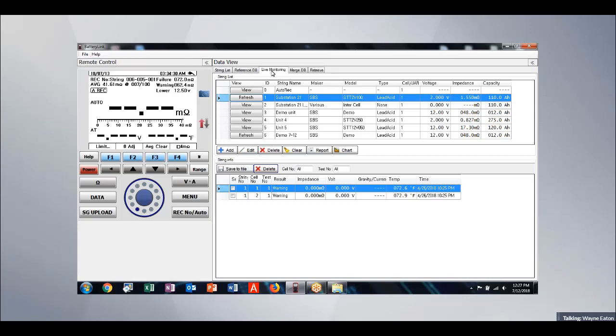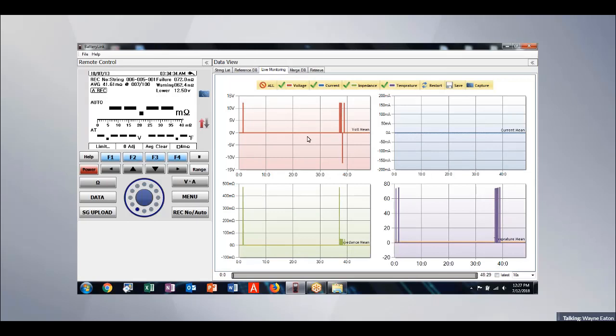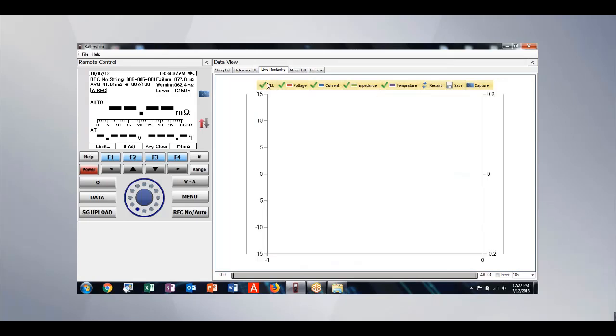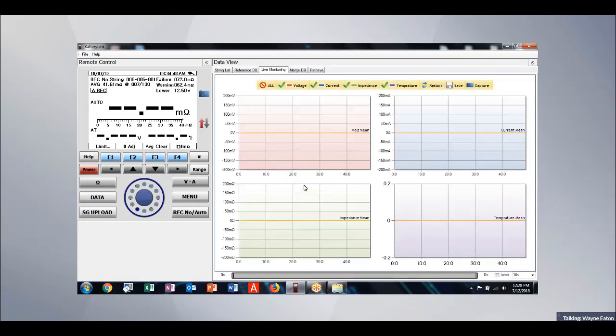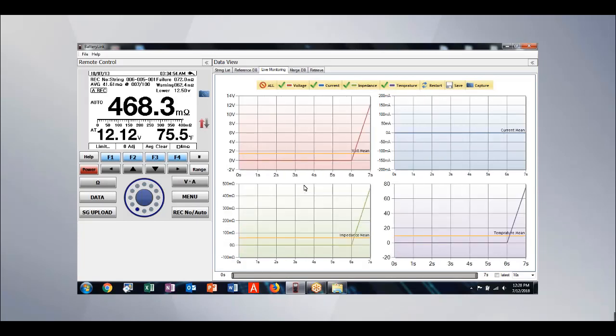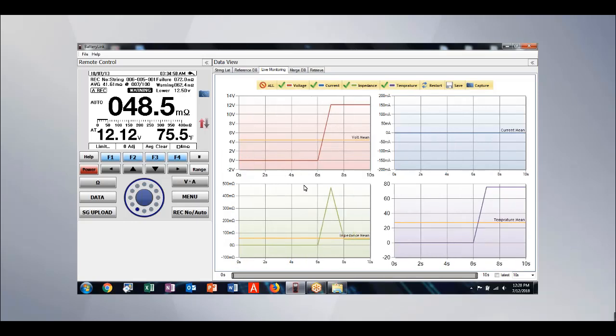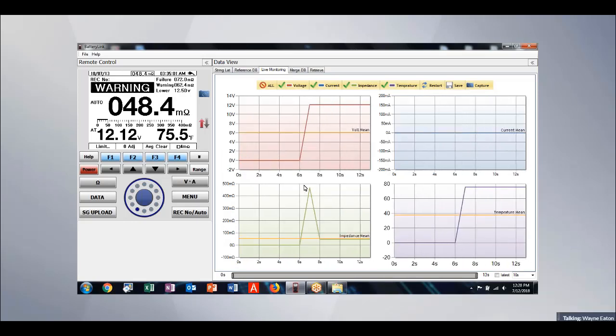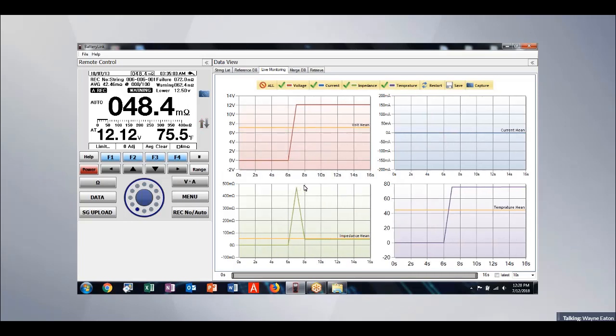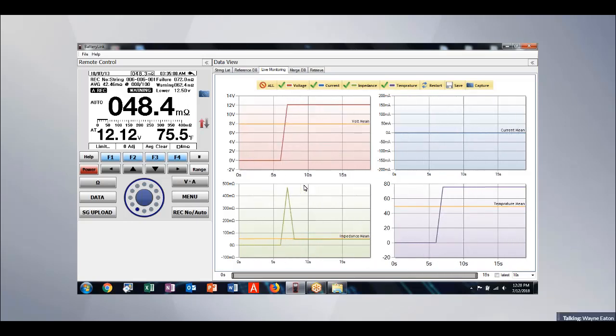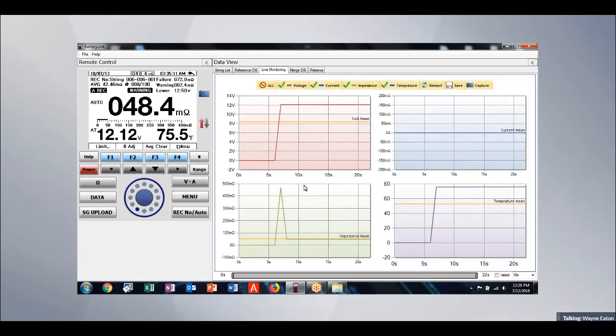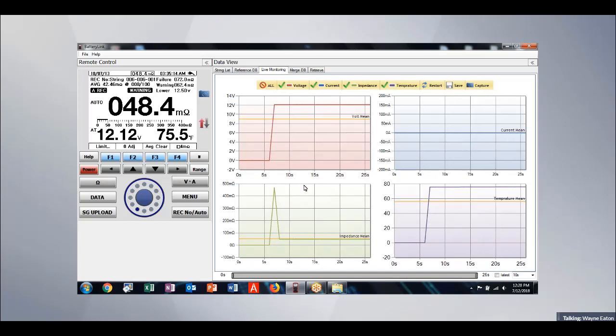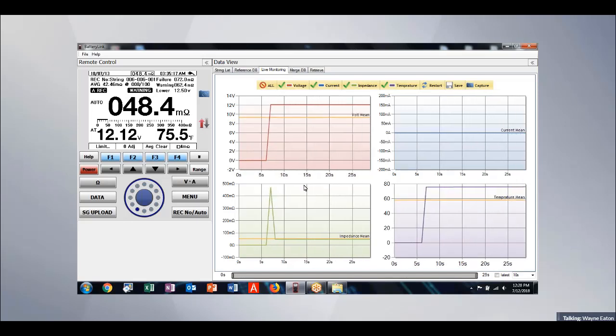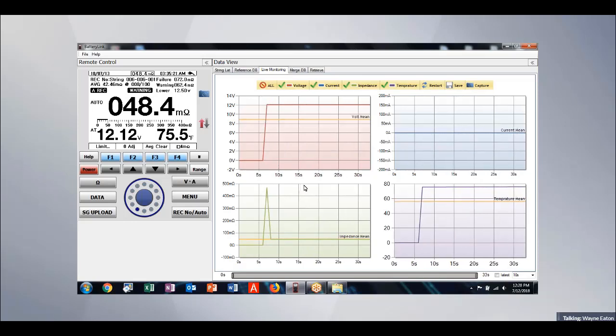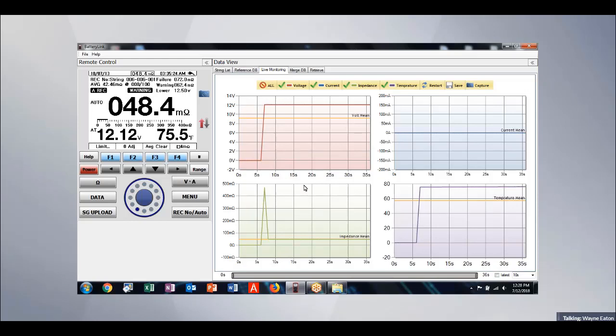One of the other really nice features of the SBS-6500 is we put in a feature called live monitoring. So if I clear this and reset it, and I get a unit connected to a battery, let's say I've got a battery that comes up as warning or fail. With this unit in live monitoring, I can actually connect the 6500 to that battery, and then I can walk over and I can turn the charger off for 10 or 15 or 20 seconds, and I can see what happens to those internal parameters, how they change as that battery goes under load. And then I can turn the charger back on and I can capture the recovery of that.